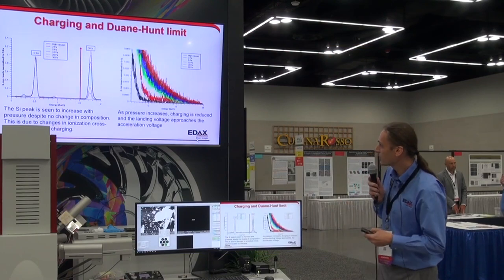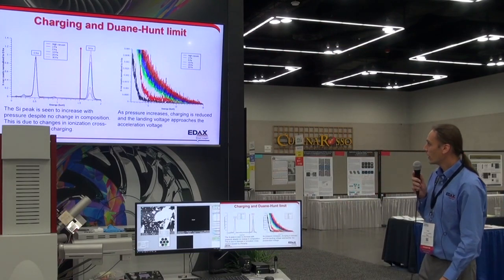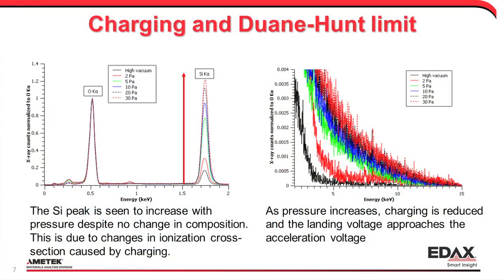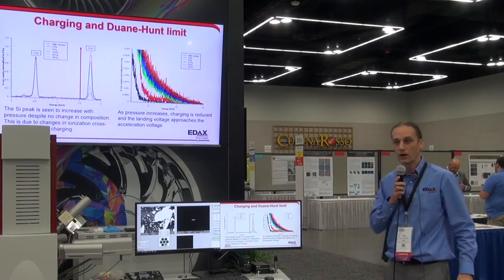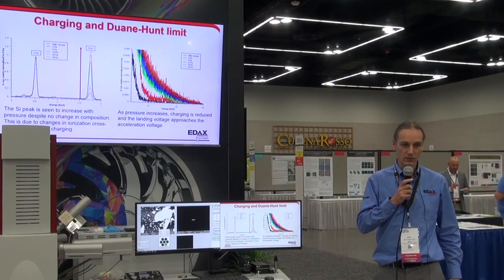This change is because I'm changing my ionization cross-section as my landing voltage changes. If we look at the background tail — I have 15 kilovolts of acceleration voltage, so my plot goes from 0 to 15 — as I go to higher pressures, the background tail stretches all the way out to 15. At 30 pascals I no longer have any charge. But as my pressure decreases down to high vacuum, that tail moves further and further in; I get more and more charge buildup, meaning my Duane-Hunt limit moves in.